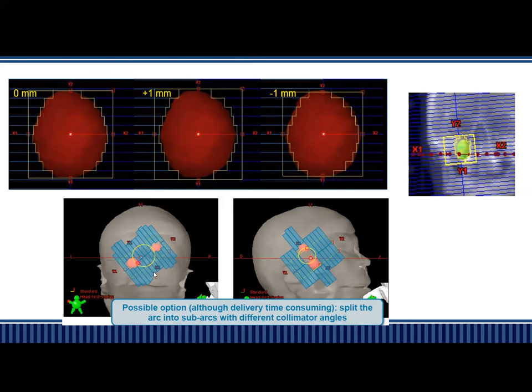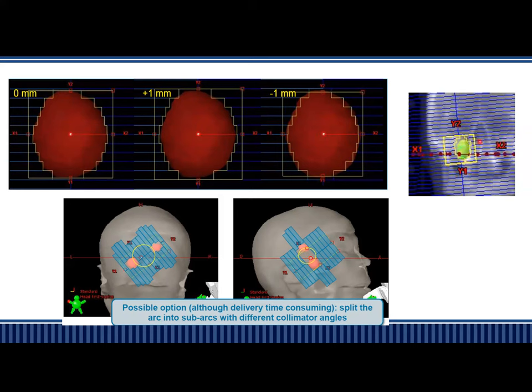Another point is collimation. If there are two volumes, try to get appropriate collimation so that it will conform the volume appropriately. Regarding JAW settings: most TrueBeam machines have a JAW tracking system, but in a small field it is not recommended to use JAW tracking — you should use a fixed JAW setting. If you use JAW tracking with smaller volumes, it may increase the number of monitor units.